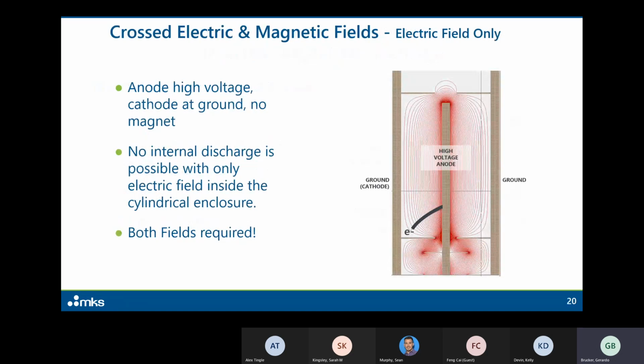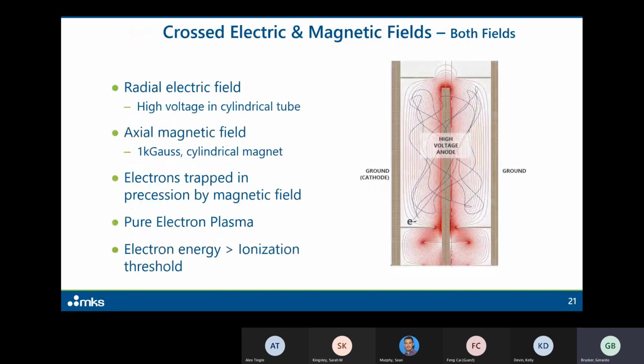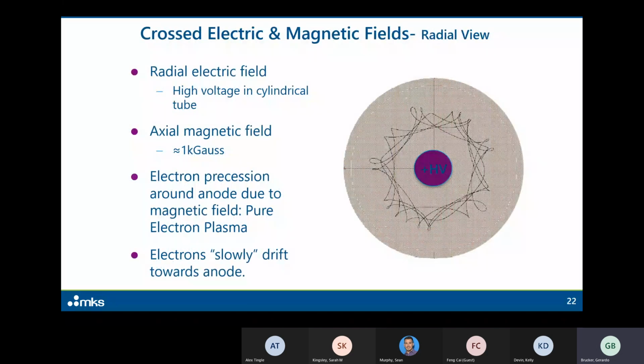The reality is, in order for a cold cathode gauge to work, you need both the magnetic and the electric field. If I took the magnet out and just turned the anode on and put an electron here without the benefit of a magnetic field, the electron will simply go to the anode and get lost. No discharge would get established. So you need a magnetic field for this to operate, right? If you add the magnetic field, this is an actual molecular simulation with an electrostatic modeling program. If you throw an electron and you have a radial electric and an axial magnetic field, the electron will start precessing around the anode. So what you end up with here is electrons trapped in precession. A pure electron plasma develops, and in this pure electron plasma, you have electron energy enough to produce ionization of molecules. You look at it from above, it looks something like this.